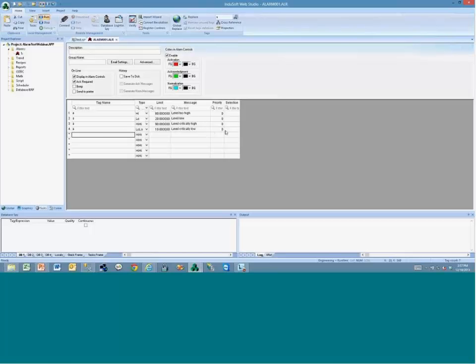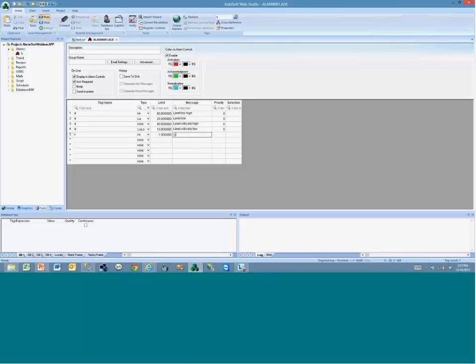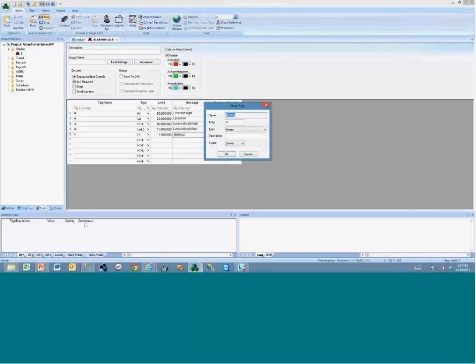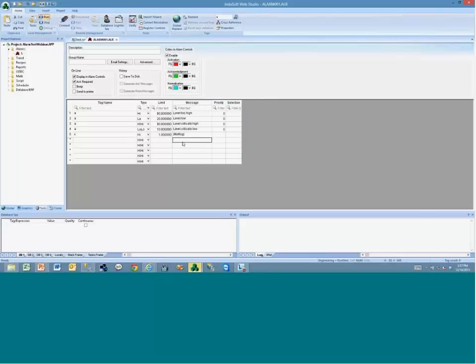And another thing that could be helpful for you as well, you could have a single tag. Let's say that if you have 0 on this tag, you have no alarms. Any value different from 0 is an alarm code from the servo. So you could have an integer tag here with the high limit 1, and the actual message is a tag between curly braces. So my message. So you can change this message dynamically during the runtime.